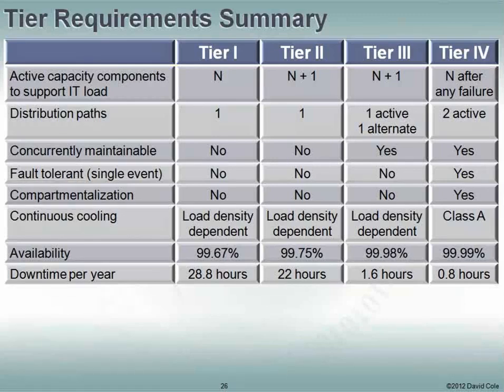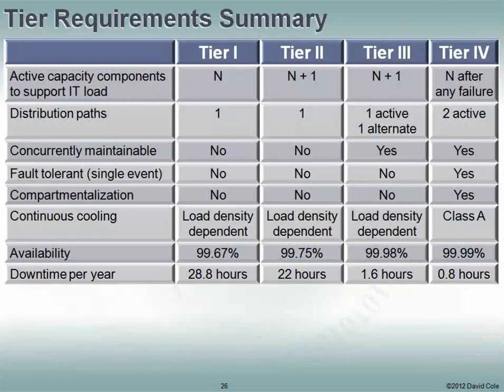At Tier 2, that goes down to 22 hours. At Tier 3, you see the big jump—from 22 hours average down to 1.6 hours. That's because of the alternate distribution paths and the concurrent maintainability. So it's very important when we look at data centers to consider availability; that's one of the key components.